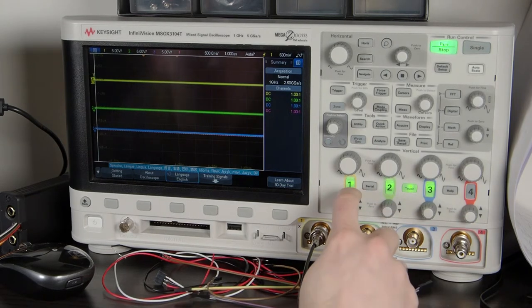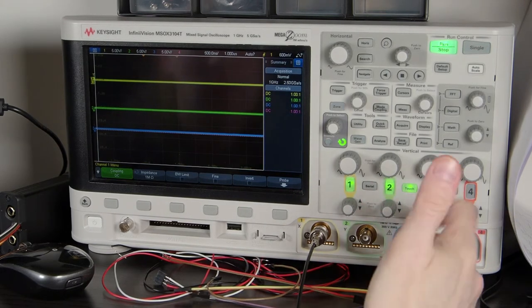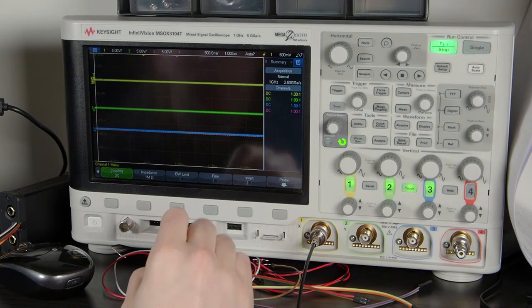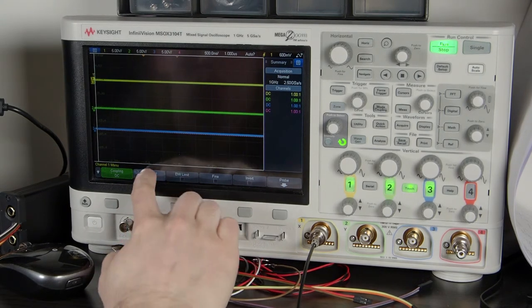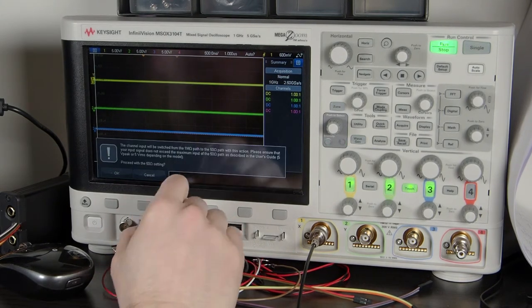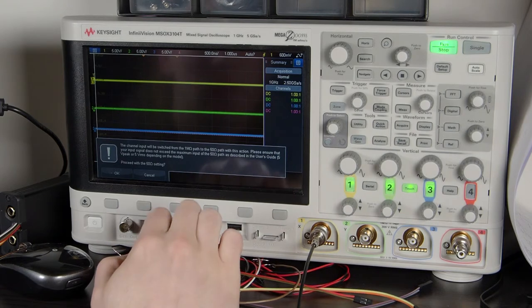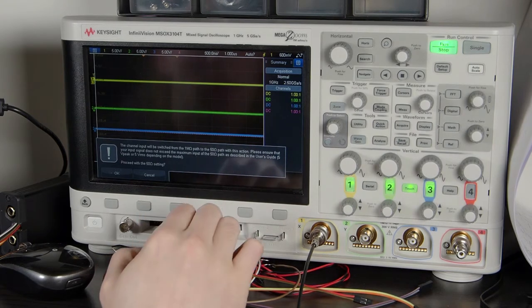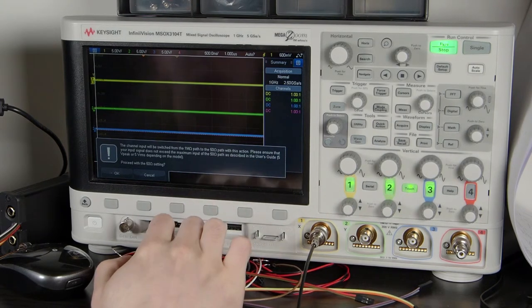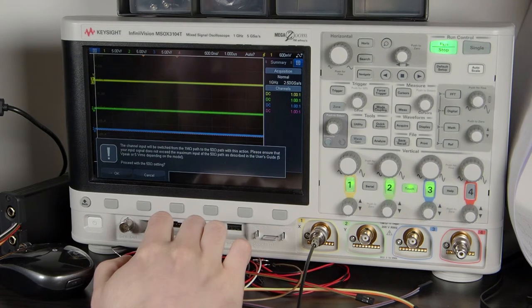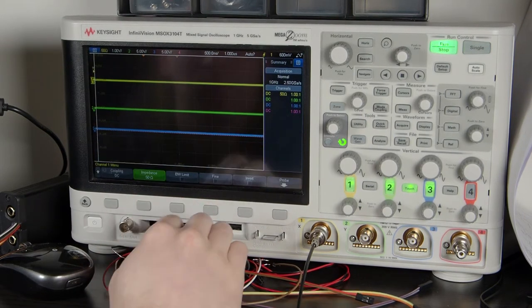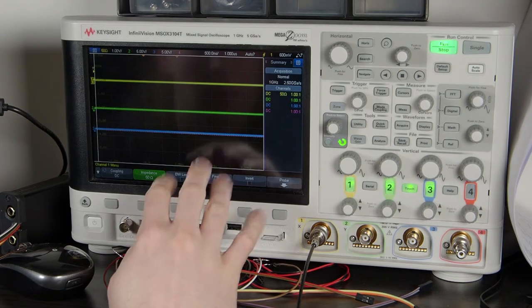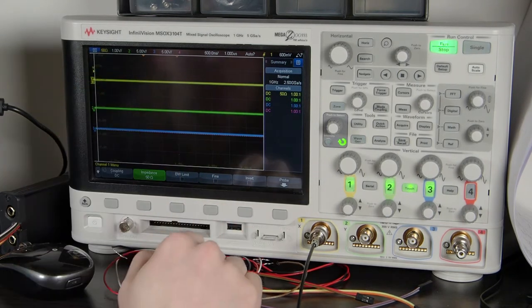So in these scopes, in the input you select 50 ohm, and then it gives a warning because there is no high impedance input at the moment. So you need to be sure that you're not exceeding the maximum voltage. But yes, it shows 50 ohms here.